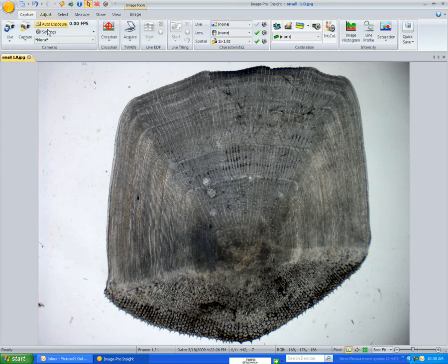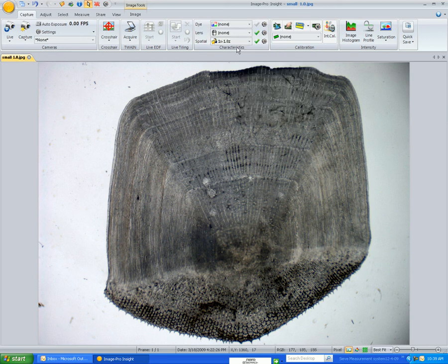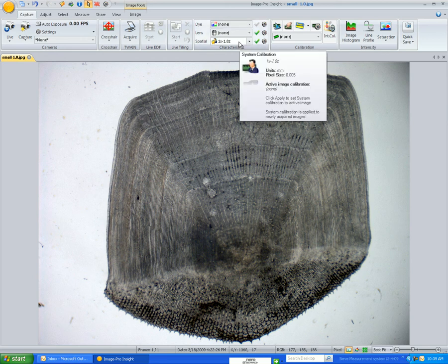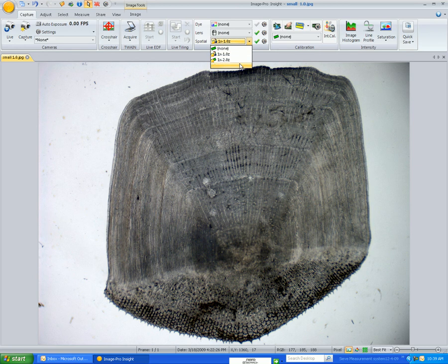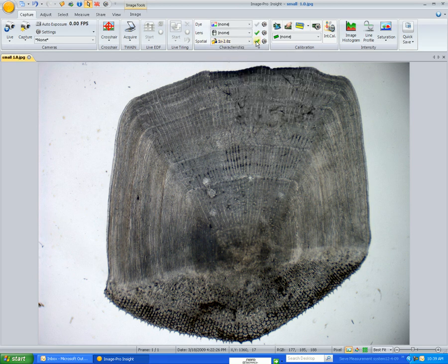I'm going to go back to Capture. Now we're going to have a bunch of calibrations saved based on the zoom setting in the front lens. They'll be in a pulldown menu here. Let's say this is what we were set to when we captured the image of the scale — if I click on this, it has now applied the calibration to the scale.